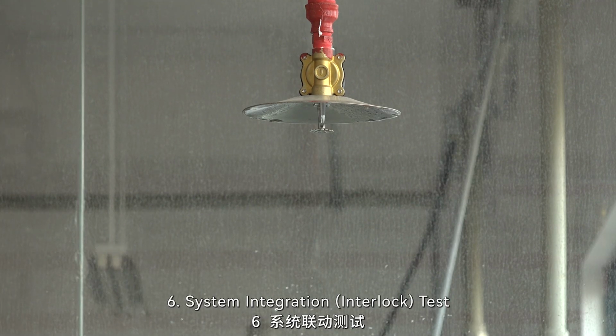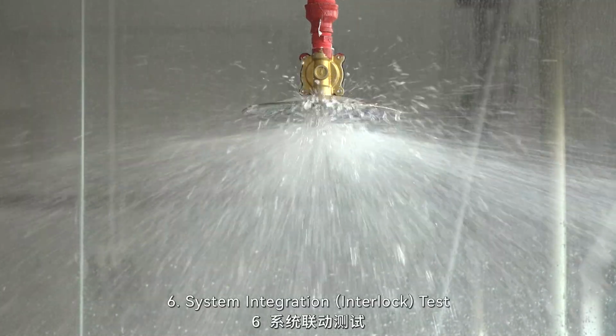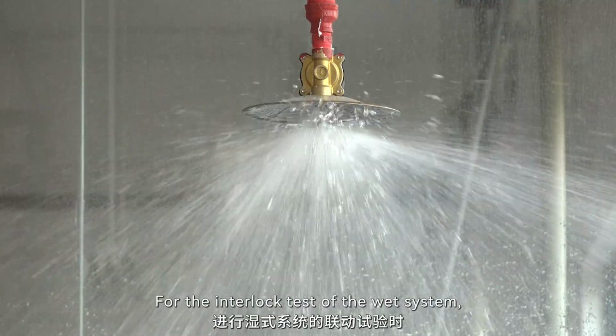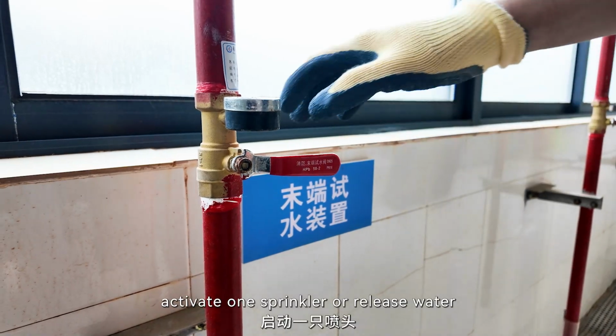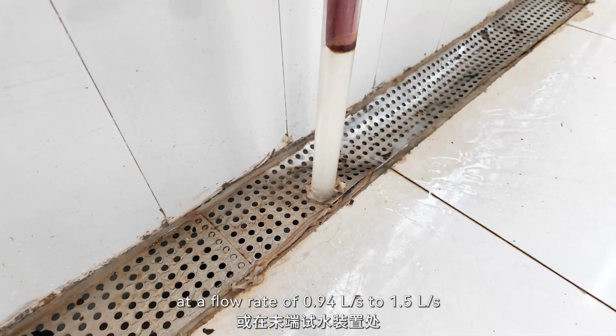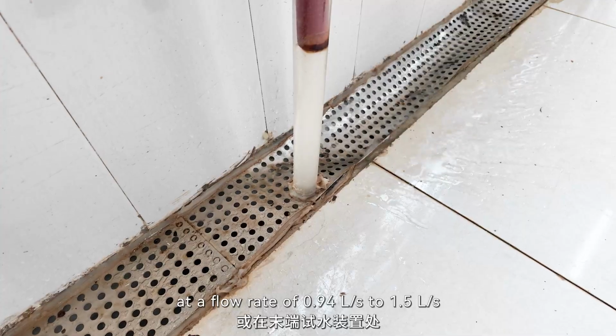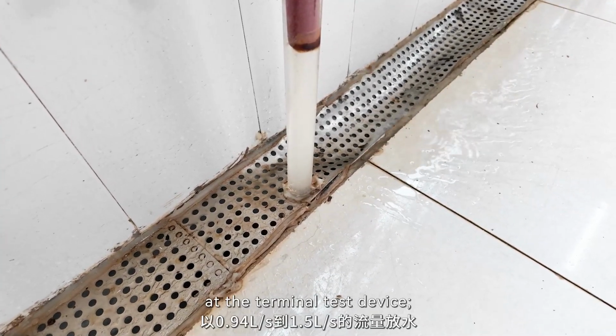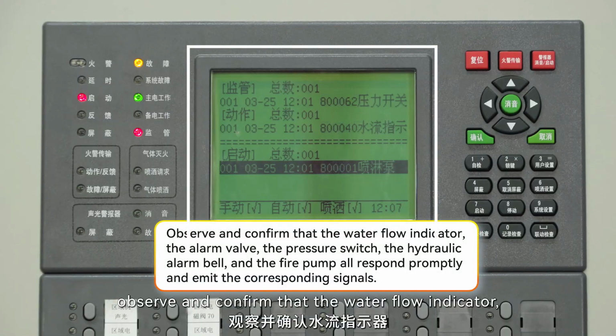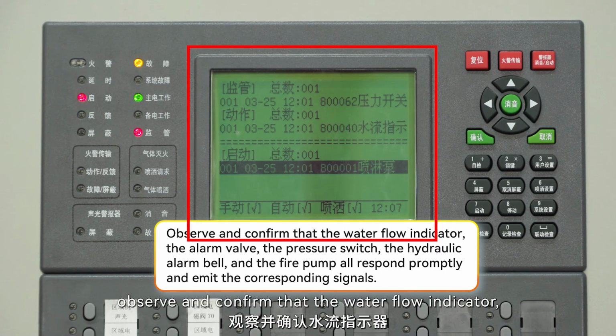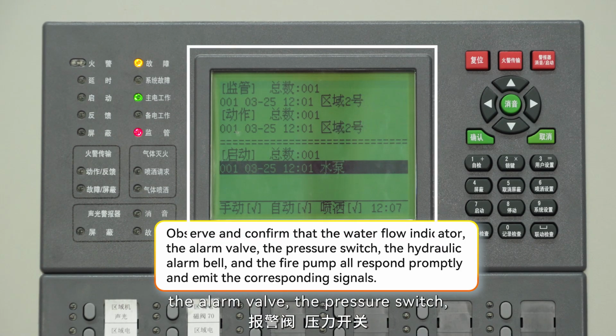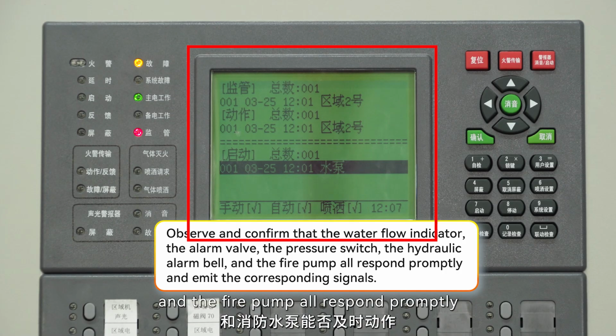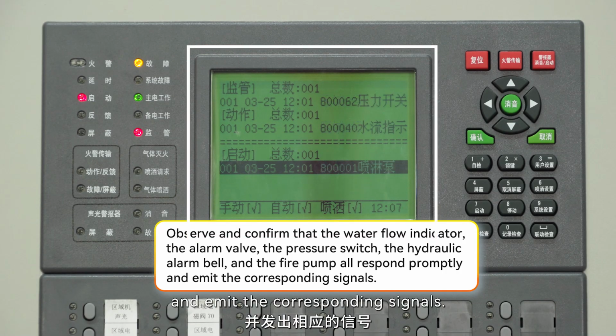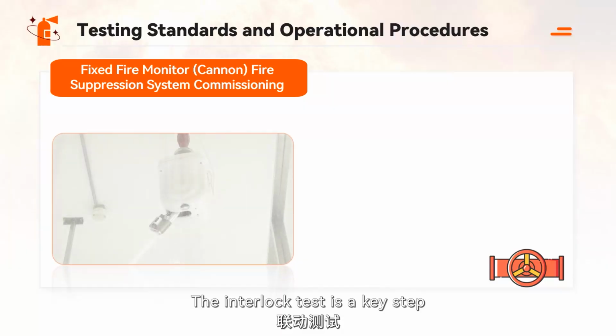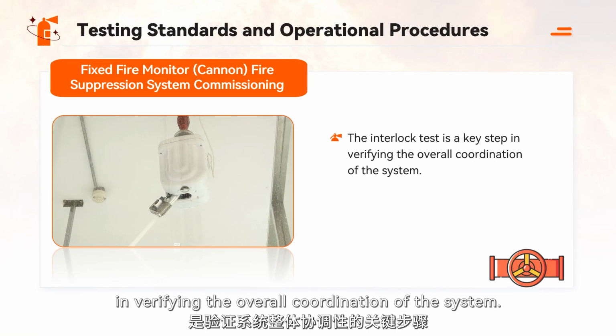6. System integration, interlock, test. For the interlock test of the wet system, activate one sprinkler or release water at a flow rate of 0.94 liter per second to 1.5 liter per second at the terminal test device. Observe and confirm that the water flow indicator, the alarm valve, the pressure switch, the hydraulic alarm bell, and the fire pump all respond promptly and emit the corresponding signals. The interlock test is a key step in verifying the overall coordination of the system.